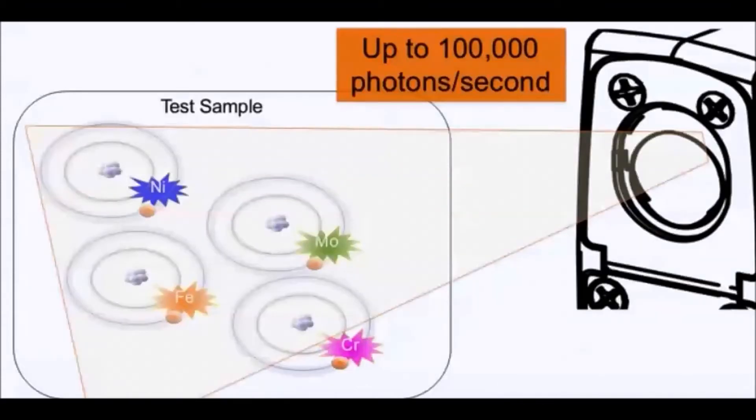While the slide diagrams that we've been looking at show single atoms, in reality tens of thousands of signature X-rays are captured by the detector every second. As long as the sample's surface is representative of the entire sample, fast, accurate, and quantitative results can be achieved in just a few seconds.